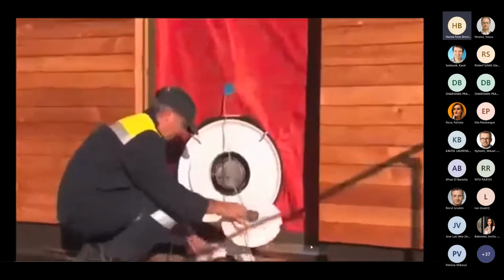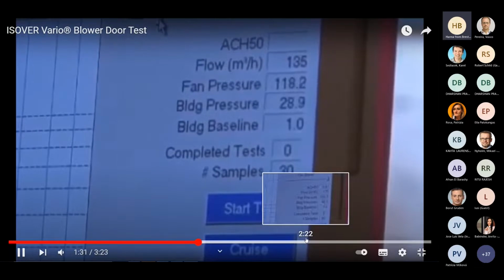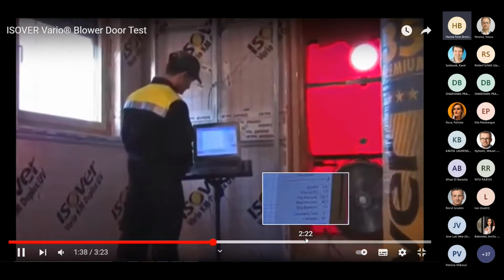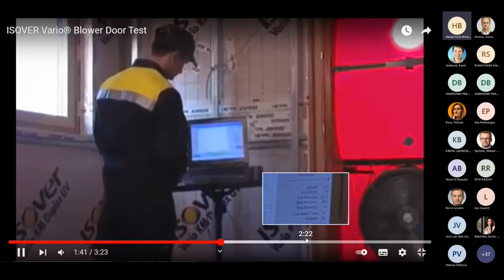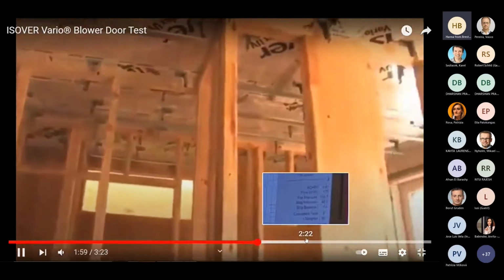The technician may change the quantity of air exchanged by using various cylinders on the blower. The building envelope could be compared to an elastic membrane reacting to pressure differences. The computer measures and displays the different response times. A series of air exchange values is recorded, which correspond exactly to the volume of air escaping from the building. The relation between the air exchange established at a pressure difference of 50 pascals and the volume of a room provides the N50 index. This value represents the percentage of total renewals of the room's air volume in 1 hour at a pressure difference of 50 pascals. Experience has shown that it's useful to combine the blower door test with IR thermography, as this is a method of making leaks directly visible. At this stage of the construction work, the Vario membrane is still accessible. Therefore, small corrections with the Vario tape are possible.